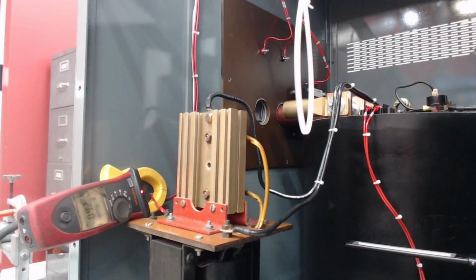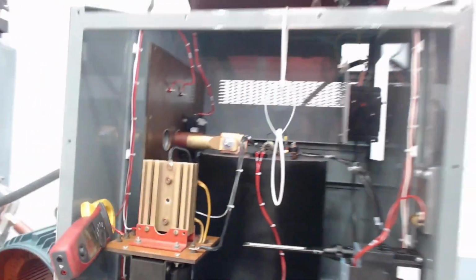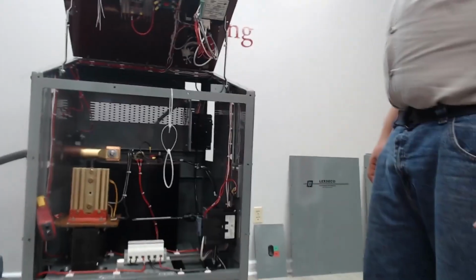There wasn't a whole lot to the circuits, so we've sort of gone over the voltage drop and the power. Once again, when you're testing these units, just be careful not to touch anything. Our new units, with the new design, are much better for allowing you to safely troubleshoot versus any of your older designs where you're having to reach down into the unit. Just do your best to not touch anything that's possibly live at all. But yeah, I think that's everything we got.